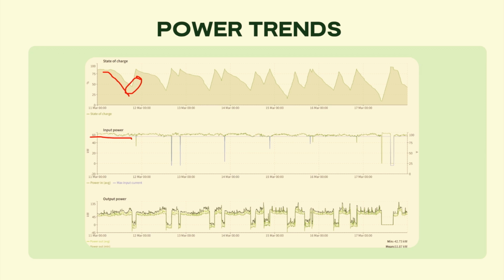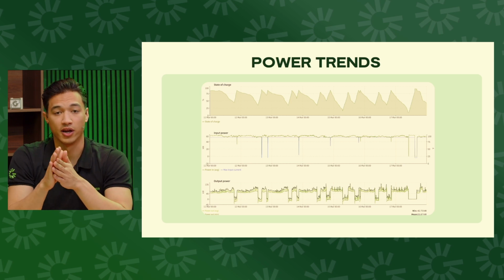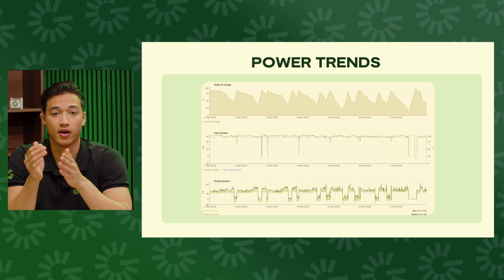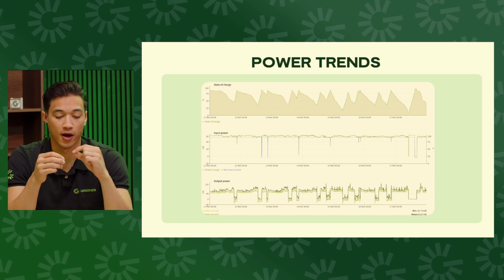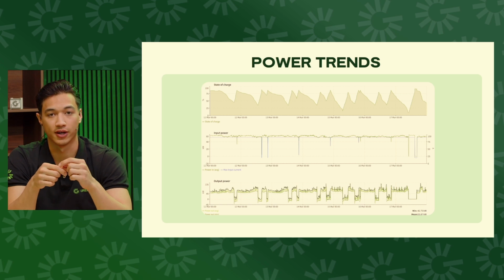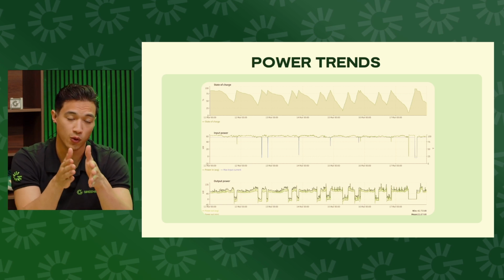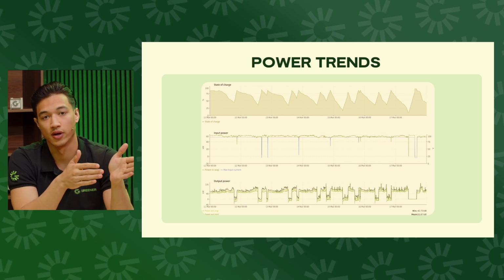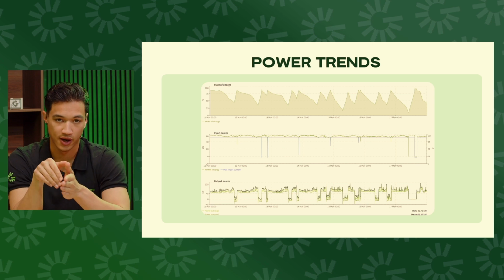So that's why you see on the output over here that first we are delivering around 45 kilowatts. And then the load drops over here, and there's negative energy being pushed into the battery, which causes the state of charge to go up here again. And we just keep repeating that. What we also did in this case is we installed a night mode. Because we were in a city, the generator wasn't allowed to be turned on during the night. So we make sure that the battery is full before 10 o'clock, and then the generator doesn't get turned on the whole night and only gets turned on when it's morning again.